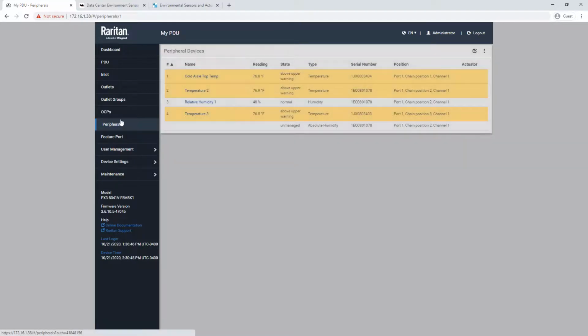Now, if I go back to my peripherals menu, you can see that all of my sensors have crossed that upper warning threshold, so they're all in a yellow warning state. This will display in the web UI, but also on the controller of the PDU or Smart Rack controller to alert you of a warning, and you can view that warning on the PDU controller by paging through the menu for specific details.